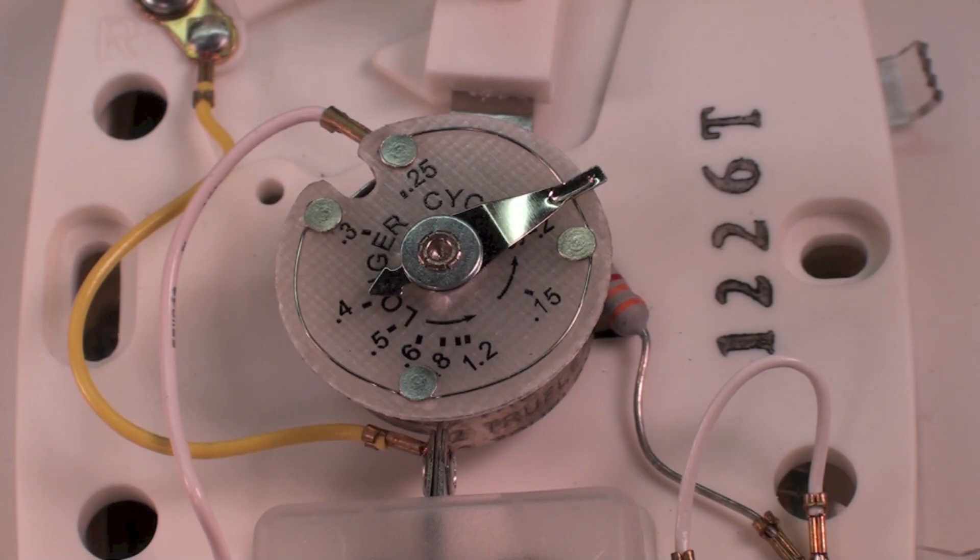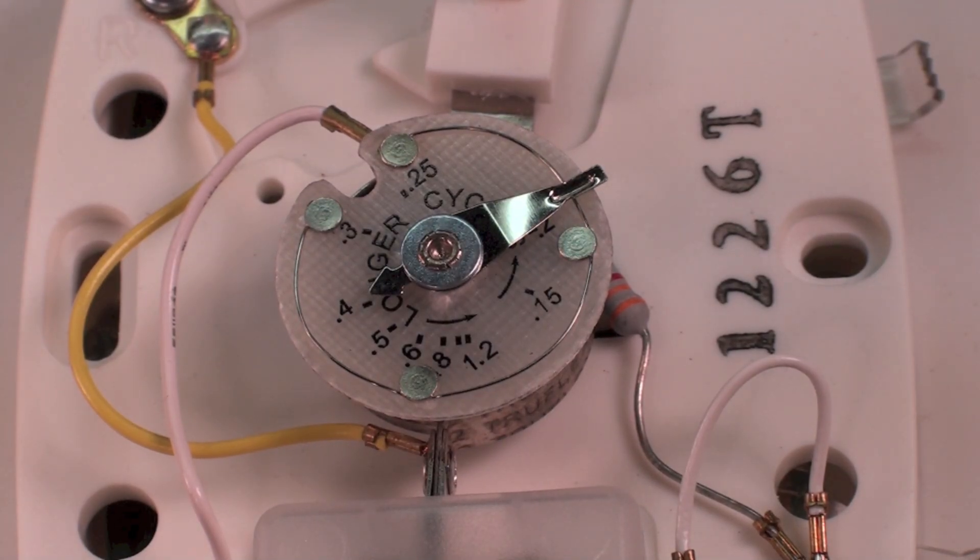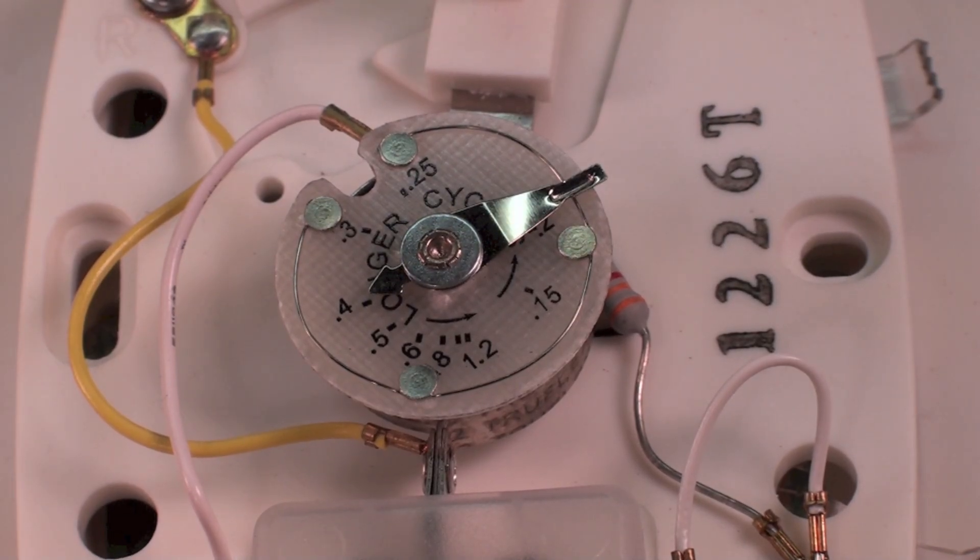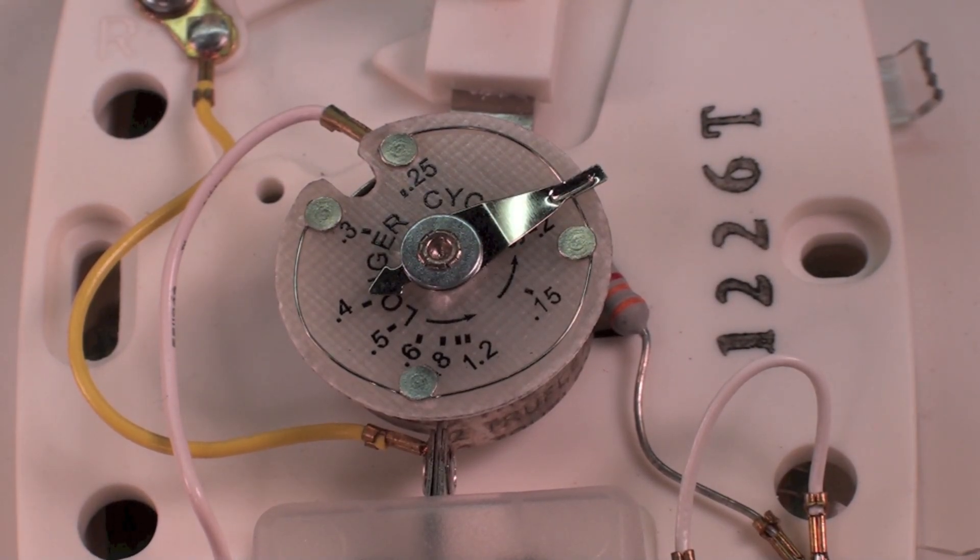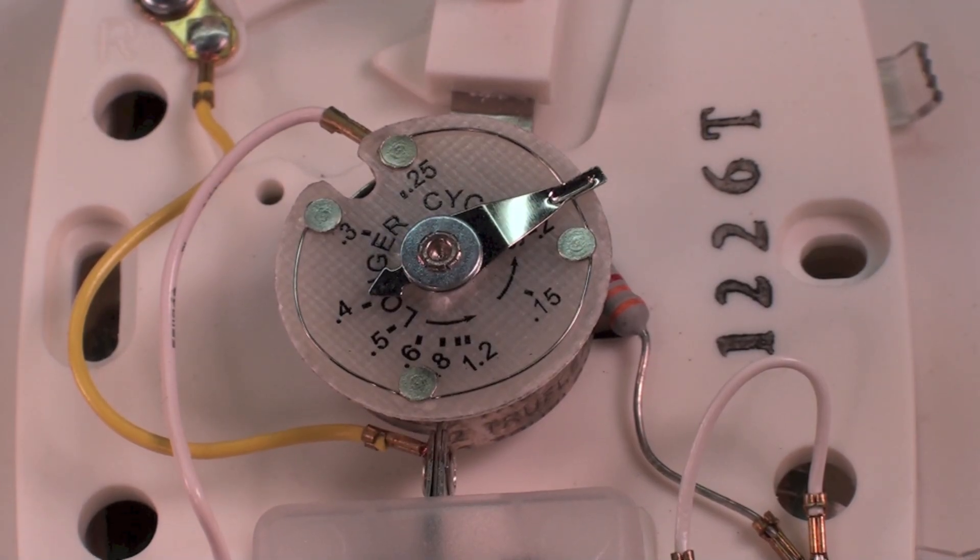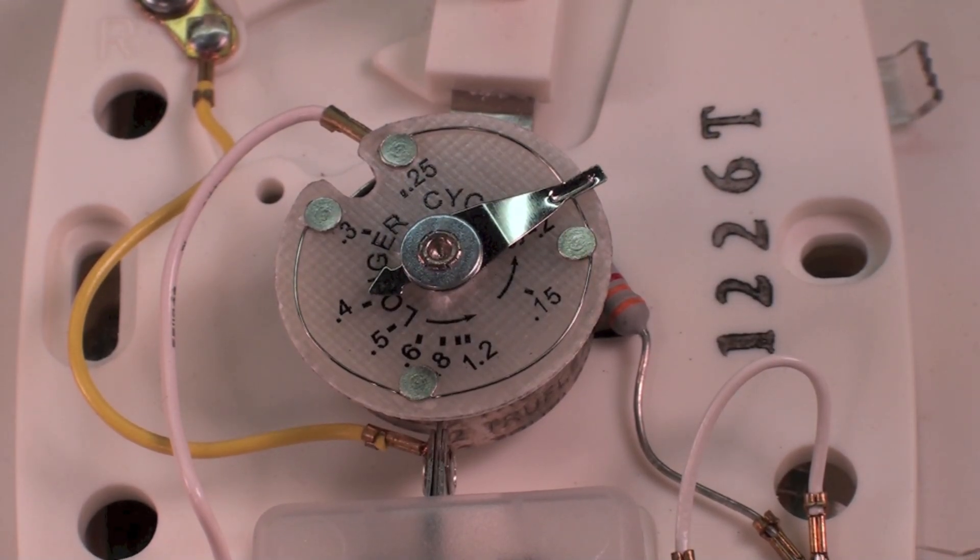If it was cycling too short, where it was only cycling for just a minute or so and then shutting off, I would move it towards longer cycles, a quarter inch at a time.